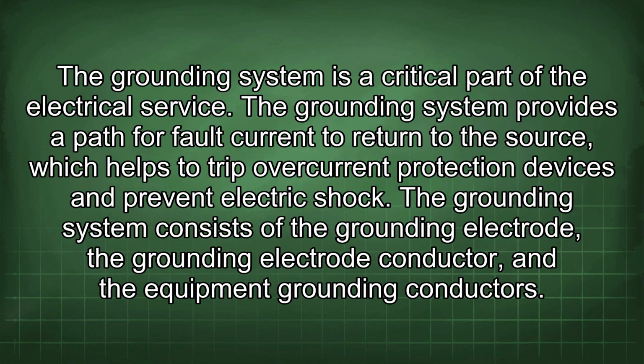The grounding system is a critical part of the electrical service. The grounding system provides a path for fault current to return to the source, which helps to trip overcurrent protection devices and prevent electric shock.